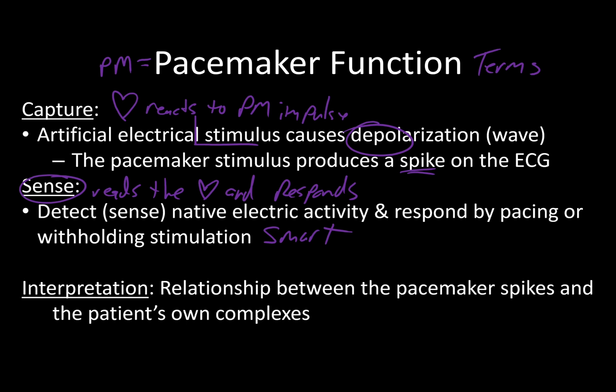Whereas if it's looking and it sees, okay, you've not done anything on your own, I'm going to go ahead and create an impulse, so hopefully we get capture, etc. That's what this is all really getting about, and it's that ability to withhold stimulation if that's what it's programmed to do.